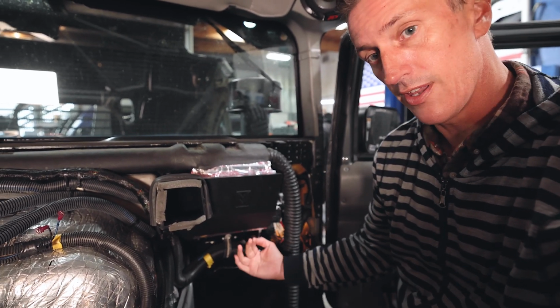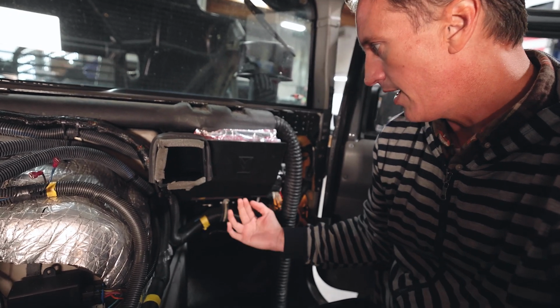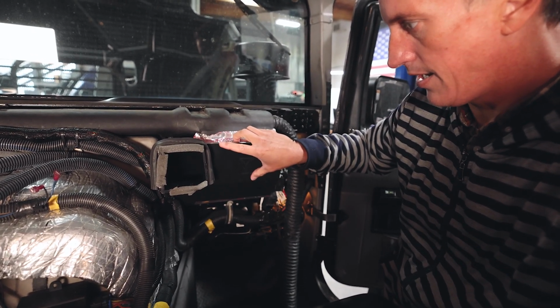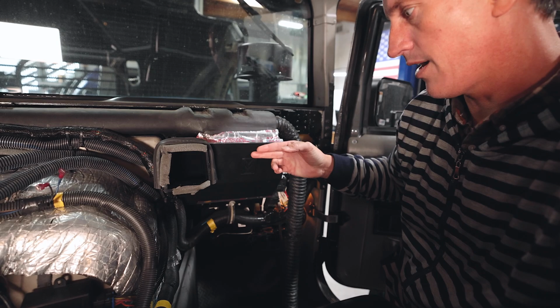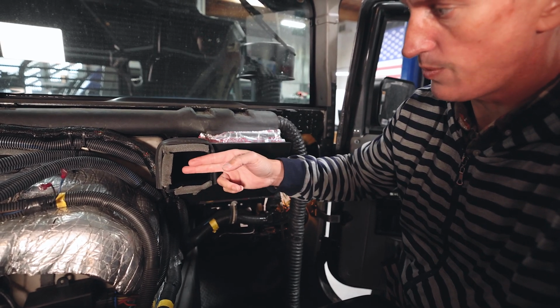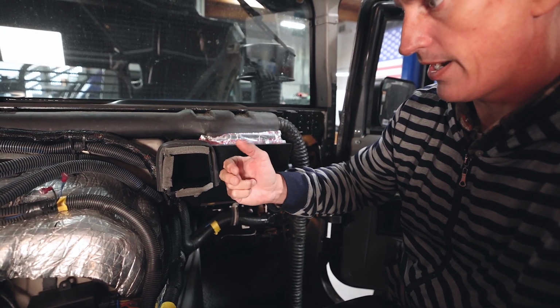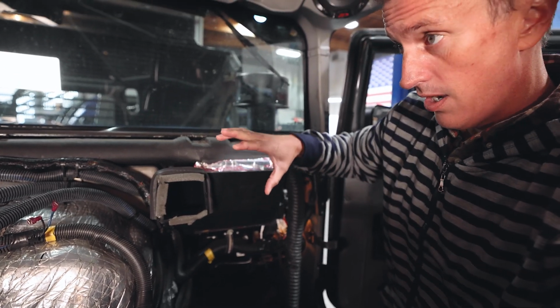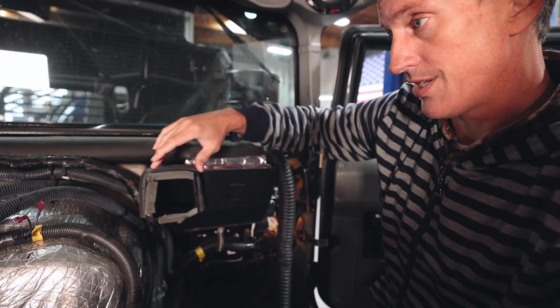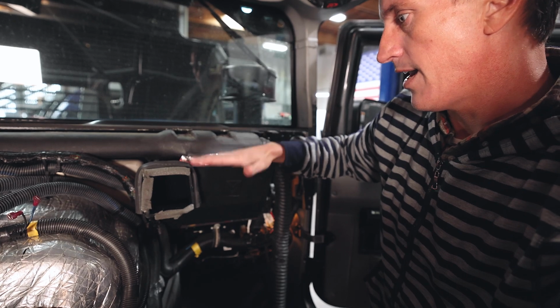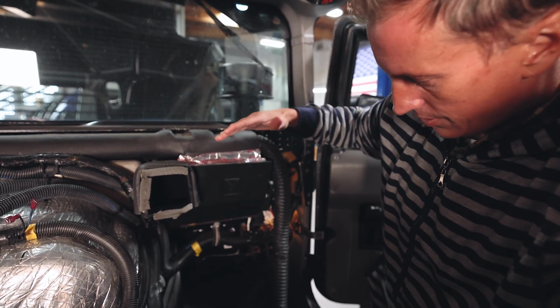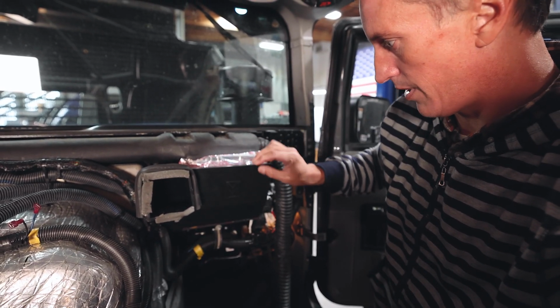So you have the ventilation, the airflow coming up like this. It gets jammed into this little pocket in here, then it has to make a hard 90-degree turn this way, then a 90-degree turn this way, and then it enters into this plenum system that goes across here. So severely inadequate airflow coming out of this contraption that they've custom printed and designed.